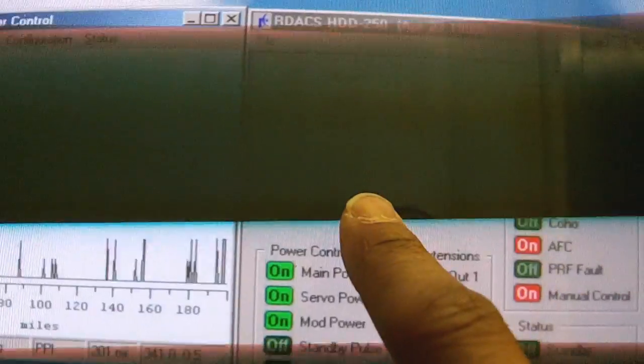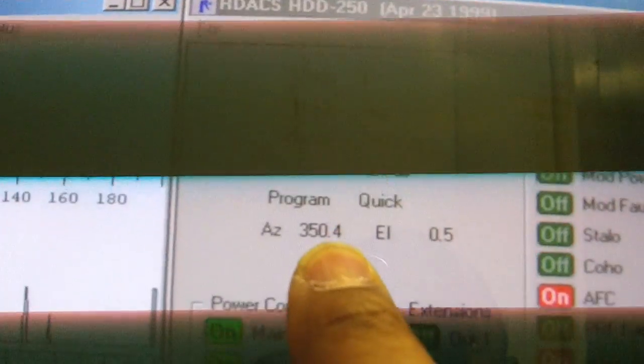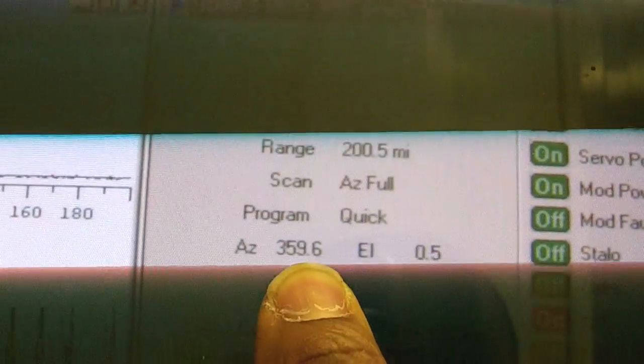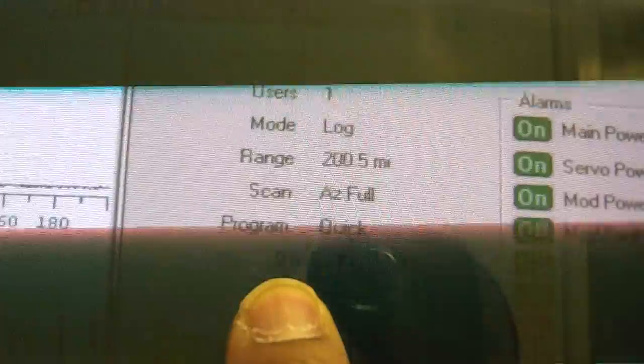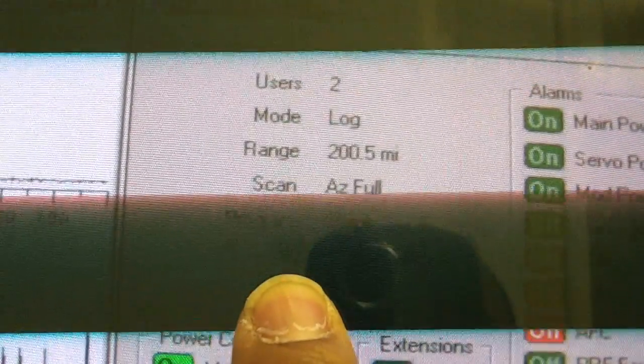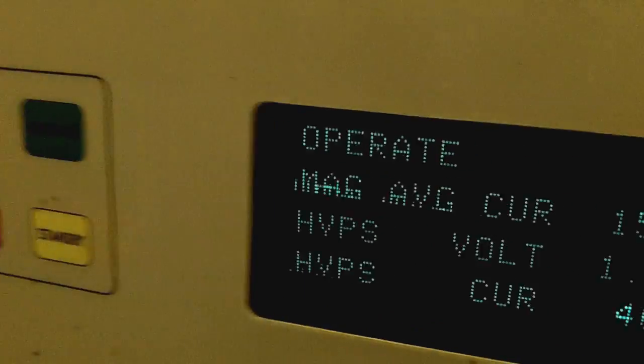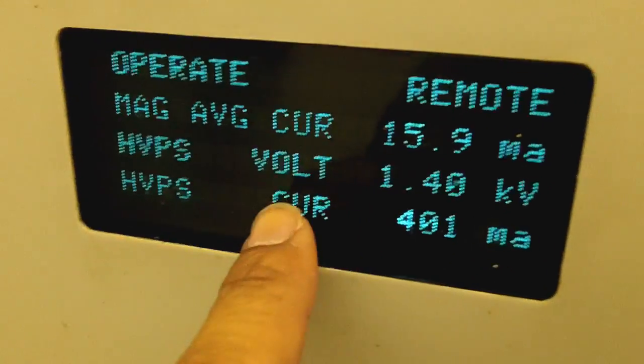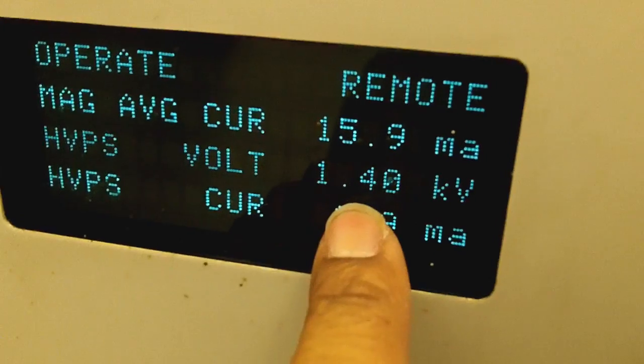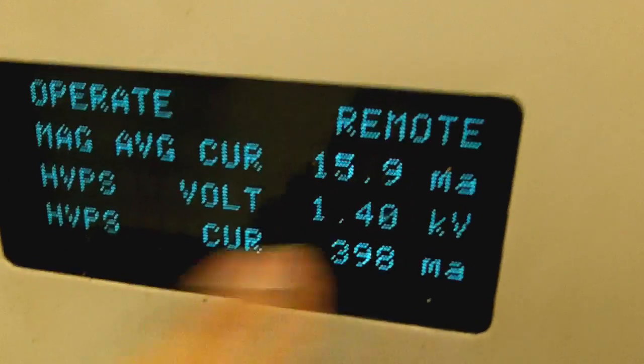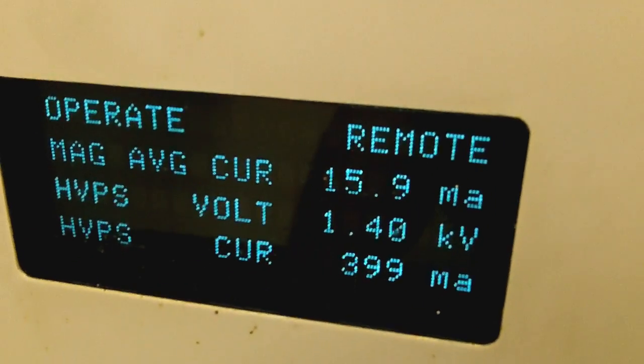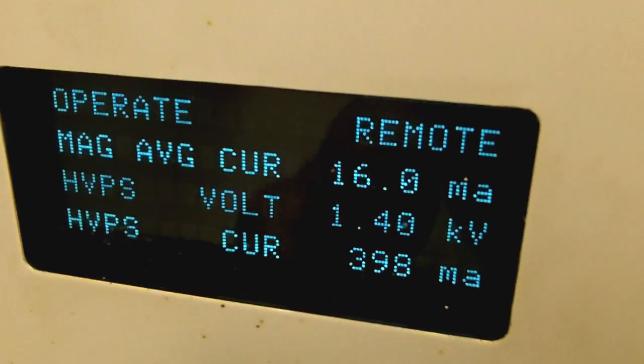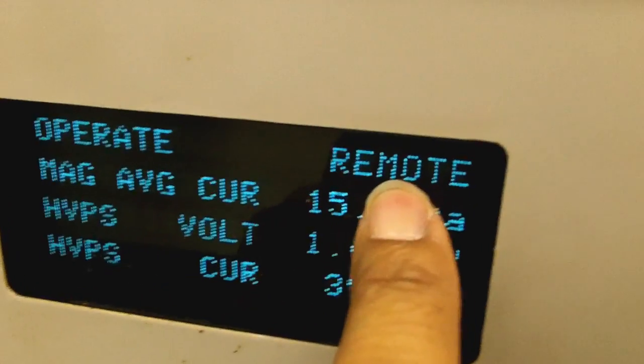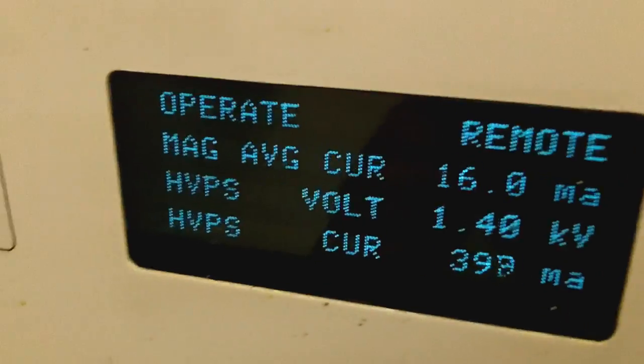And we should have radar echoes because it's raining outside. See right here, we still have azimuth rotation, so the radar is spinning right now. Starts over at zero, goes all the way up to 360, and starts back over. And the transmitter is operational, everything is up, 1.4 kilovolts, milliamps, everything is correct. Remote, which goes back to the television station.